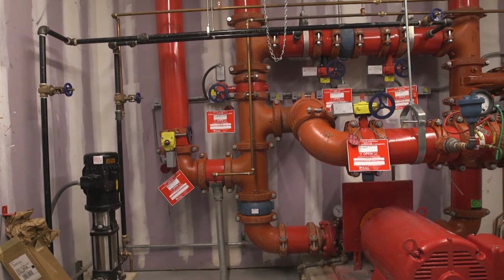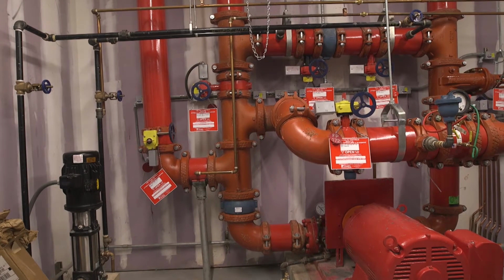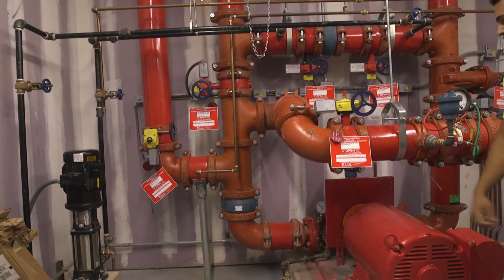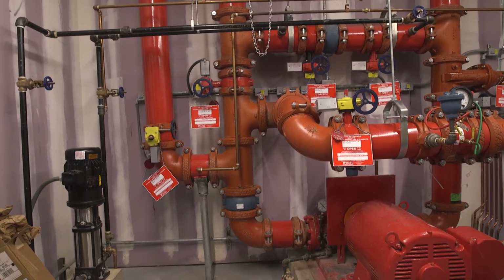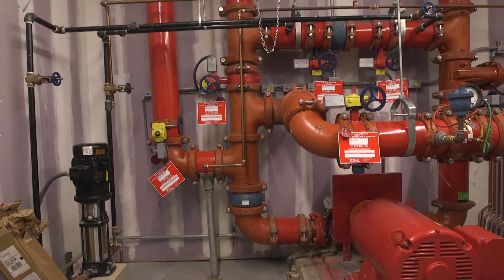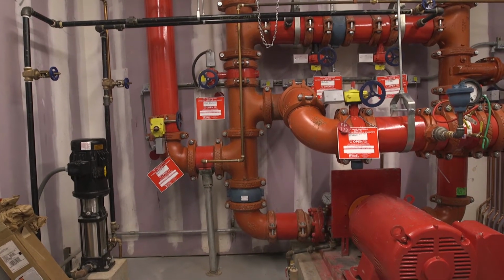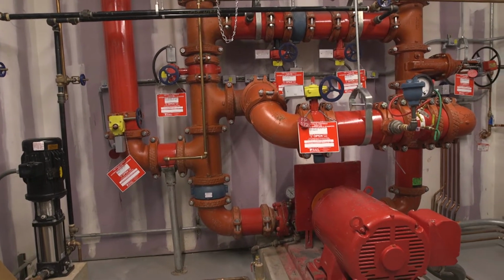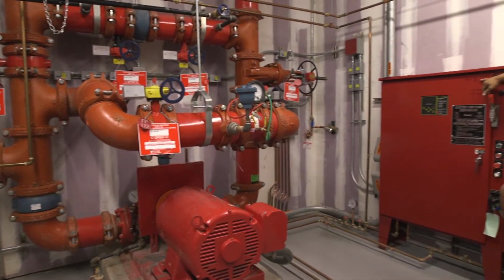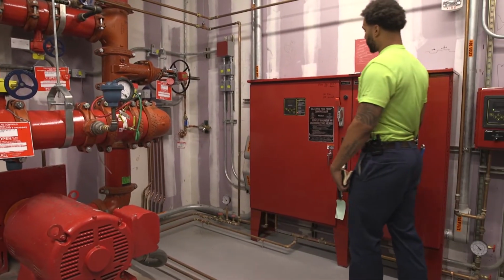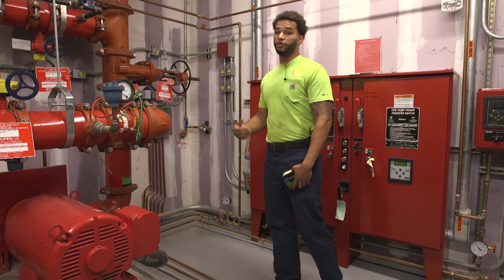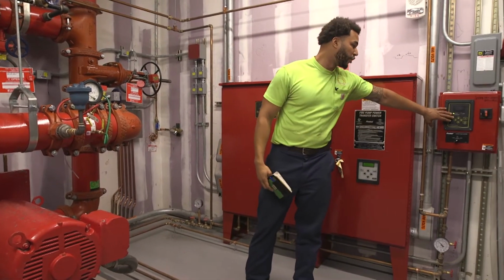So our jockey pump is our pressure maintenance device. So we will always want our jockey pump to kick on before our fire pump kicks on. So your jockey pump will also be set at 10 pounds above where your fire pump kicks on. So the fire pump's designed to kick on at 110 PSI. So your jockey pump will keep you at 120 on and 130 off.